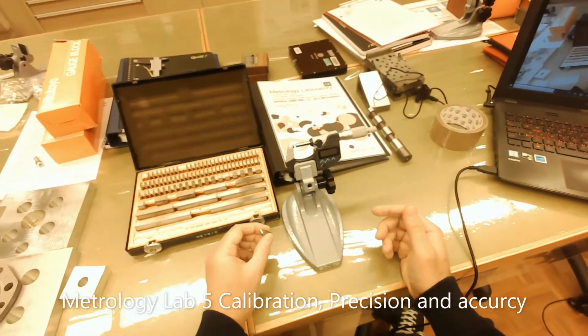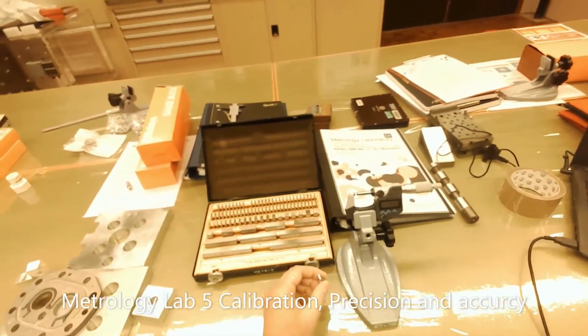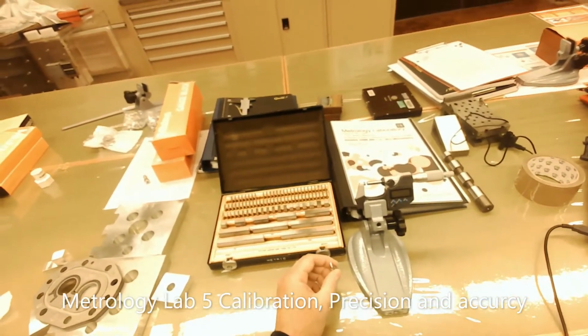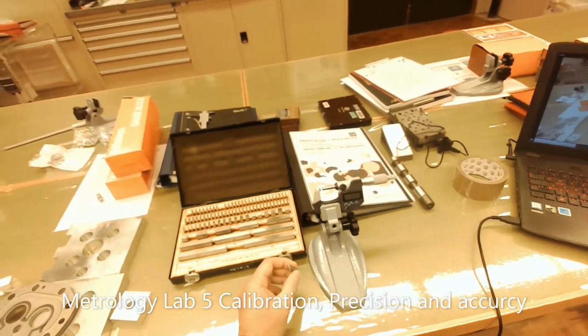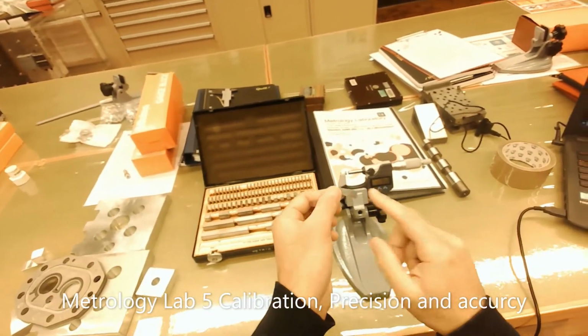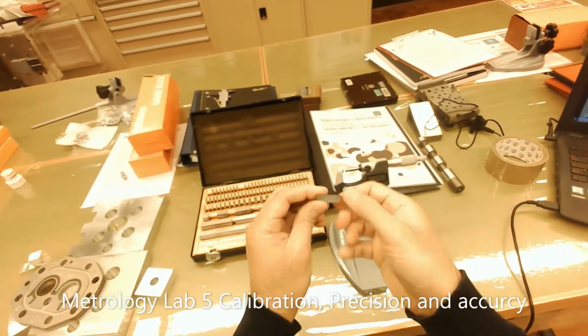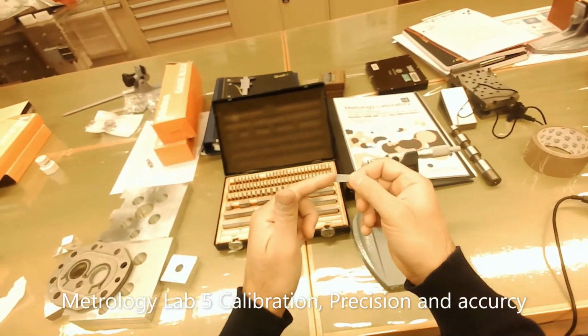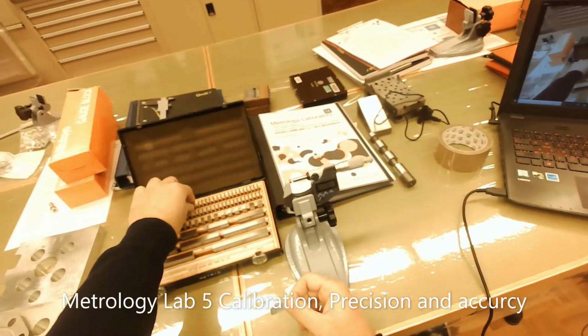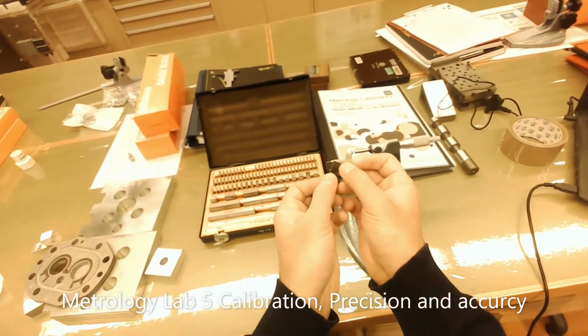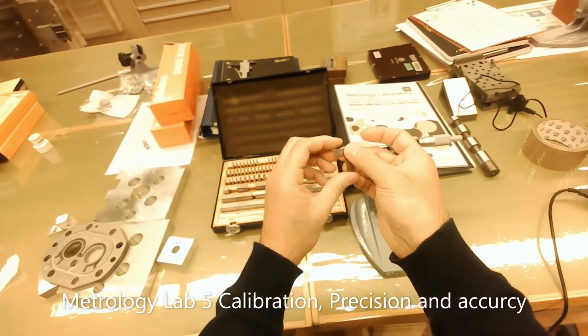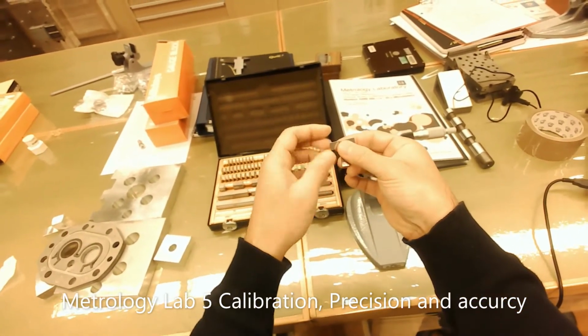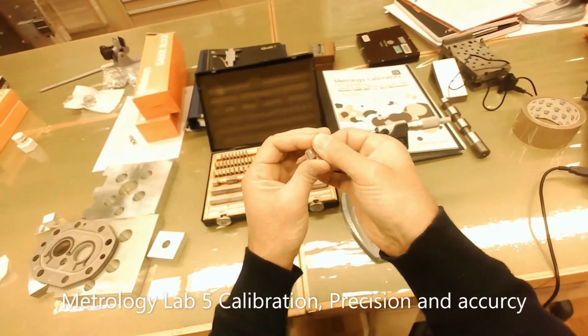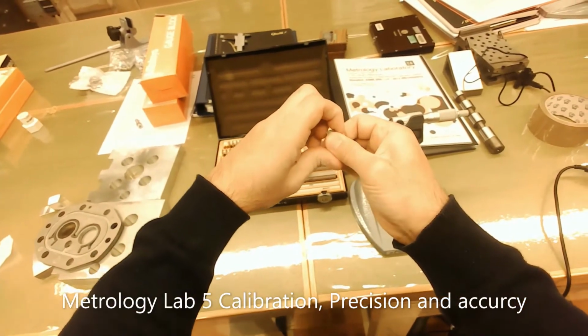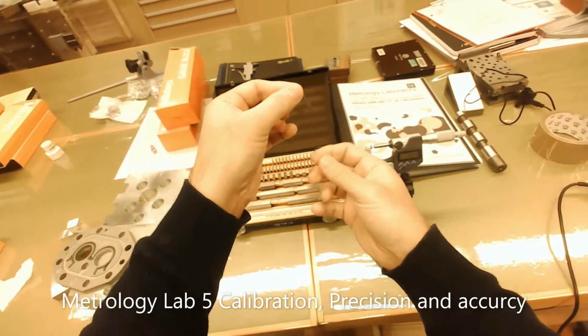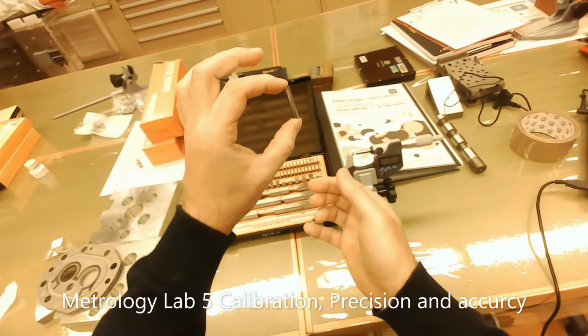They should always be kept at the temperature of the lab, which is about 20 to 25 degrees, because any other change in temperature may change their value slightly. They have a good surface finish, and this is done by the super finishing process. The main reason for the good surface is to have very close tolerances. So you can see that if I slide these blocks against each other, then twist them, it's not a magnet, but the two parts are going to be built up as one part.